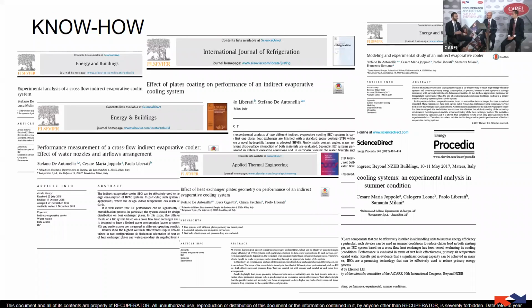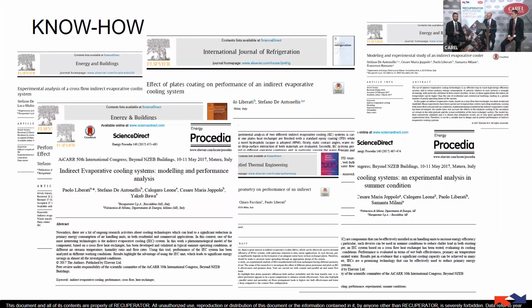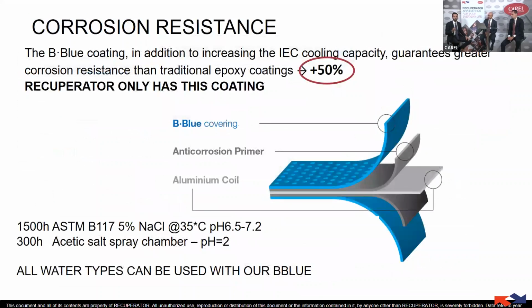Yes, because until now we have focused mainly on the cooling capacity, how to enhance the cooling capacity. But two main points are really important. One is the corrosion that we have seen before. It's important also for hygienic application, but even in this case where you're using water, it's important to have aluminum protected by a solution that is able to face the corrosion for different types of water.